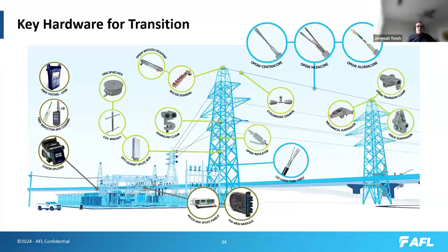All right, on to the transition to the substation. So just kind of an overview here of the materials required or helpful for this process. And I'm going to break this out into phases. So the first phase of the transition is securing your cable to the end structure. You can see on the bottom left here, 2 green circles: on the top, your optical ground wire being secured to the final structure, and then the lower green circle shows the ADSS in the underbuild position.